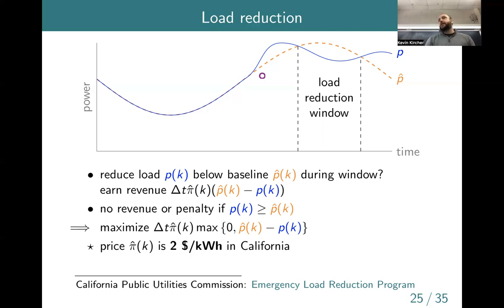Sometimes that's a utility, sometimes it's a third party. And the methods range from very simple to quite sophisticated. The typical one is very simple. It would just be like, okay, tomorrow at 2 p.m. is a Wednesday, and it's during this month, so we'll look at the last 5 Wednesdays at that hour, and we'll average that, and that becomes your baseline.